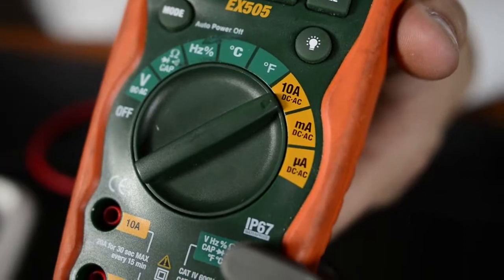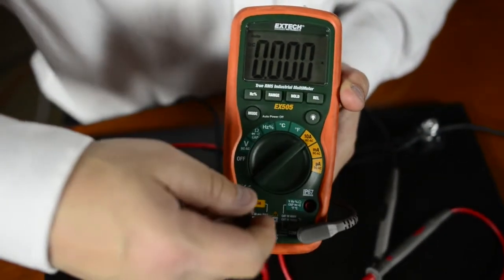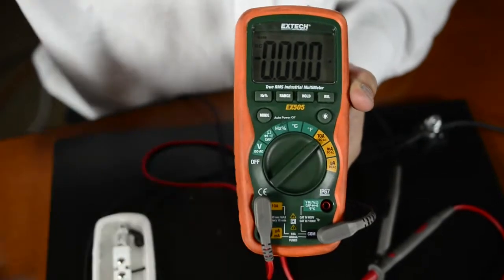Before you try to use your amp function, you've got to make sure you understand how to set your meter up. We're going to go over here to our amp function, and we have to make sure we move the red lead to the right spot. We're always going to start off on the high or the 10 amp function.